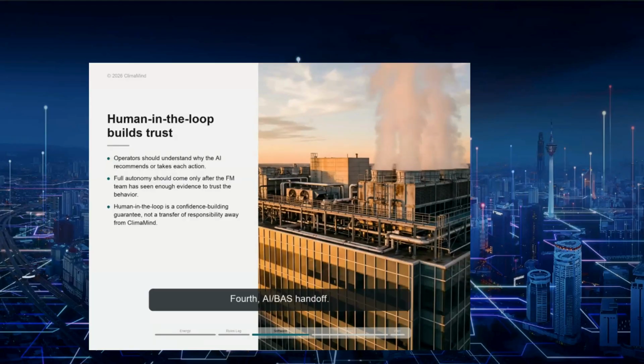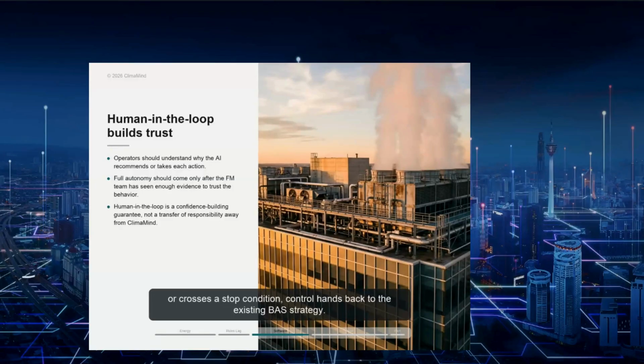Fourth, AI BAS handoff. The BAS remains the operational foundation. If the AI layer is paused, loses confidence, sees a fault, or crosses a stop condition, control hands back to the existing BAS strategy. AI becomes operationally acceptable when the control path is visible, bounded, measurable, and reversible. It also avoids extra work. Advisory validation builds evidence and trust.